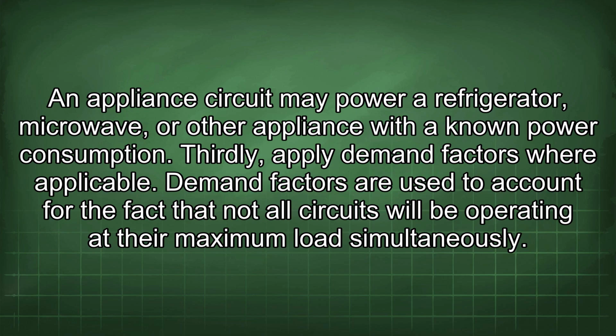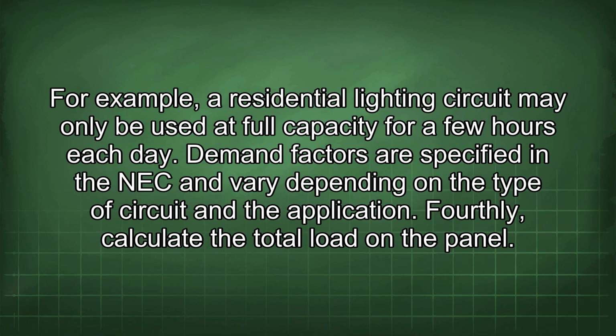Thirdly, apply demand factors where applicable. Demand factors are used to account for the fact that not all circuits will be operating at their maximum load simultaneously. For example, a residential lighting circuit may only be used at full capacity for a few hours each day. Demand factors are specified in the NEC and vary depending on the type of circuit and the application.